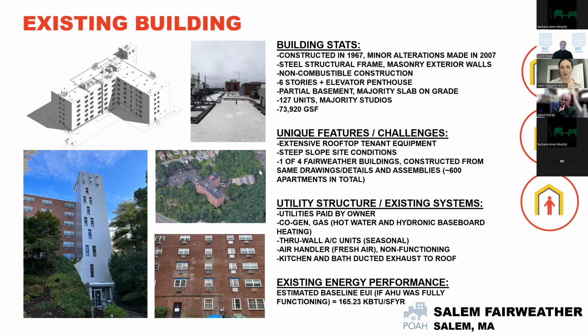The existing utility structure, everything's paid by the owner, which is definitely helpful when we're considering some of these upgrades. The building has a cogen and gas, hot water, and hydronic baseboard heating, and through-wall air conditioner units that just go through little sleeves in the building, which get capped in the winter, but it's more or less just air passing through the building. It has an existing air handler, although it's been non-functional for years, and the kitchen and bath are ducted and exhausted through the roof, which ended up being a really good thing for our solution.